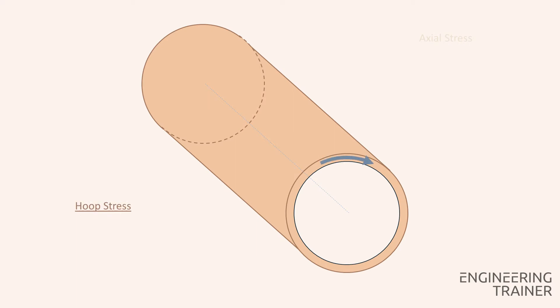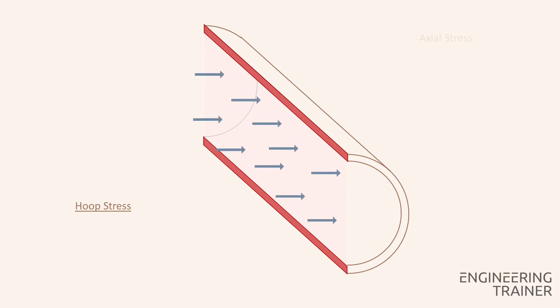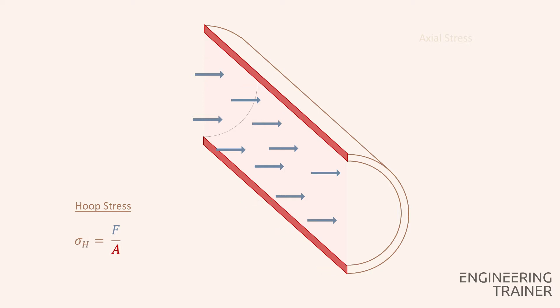Let's have a closer look at the hoop stress first. The pressure forces on the inner wall have components perpendicular to the plane of our cross section and the total force is balanced by the stress in the material. This stress can be calculated by dividing the force F by the area A. In this case we're evaluating the hoop stress sigma H. The force F can be calculated by multiplying the pressure load P times the cross-sectional area of the inside of the pipe A_P, in which A_P is formed by the pipe inner diameter and the length of the pipe piece.